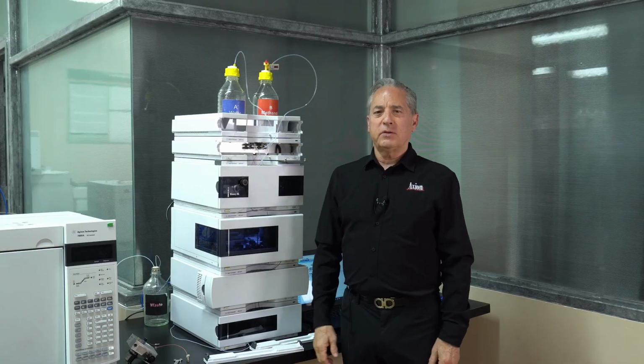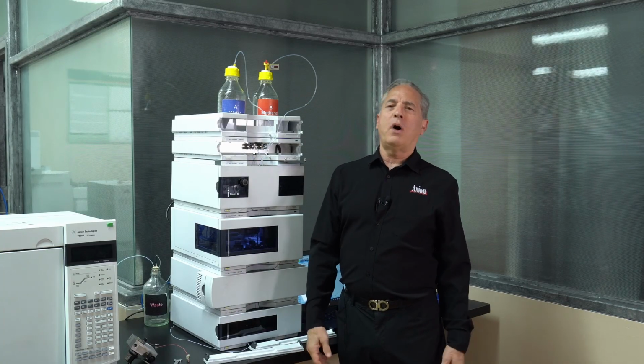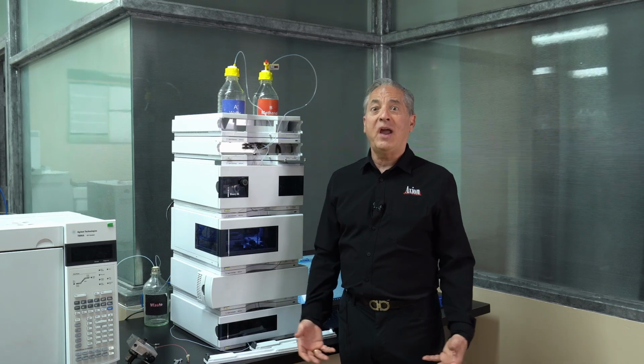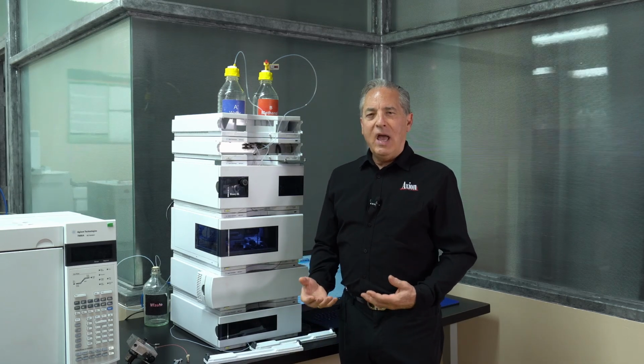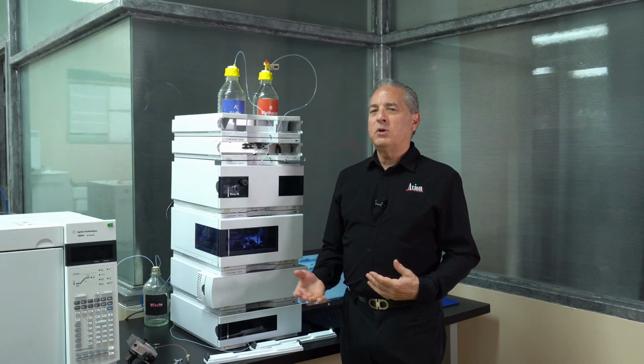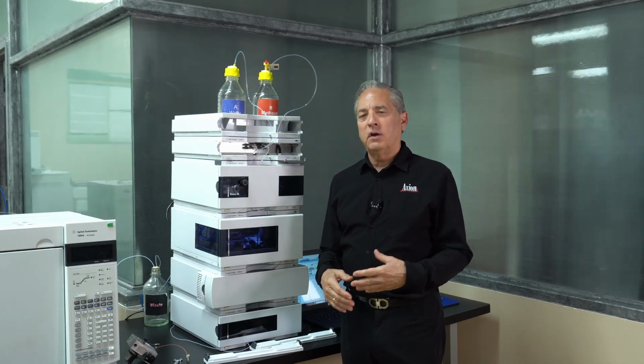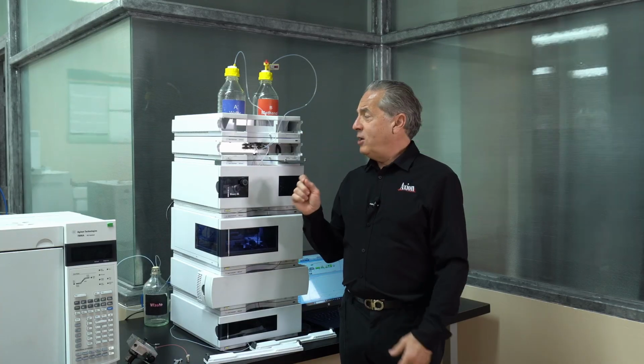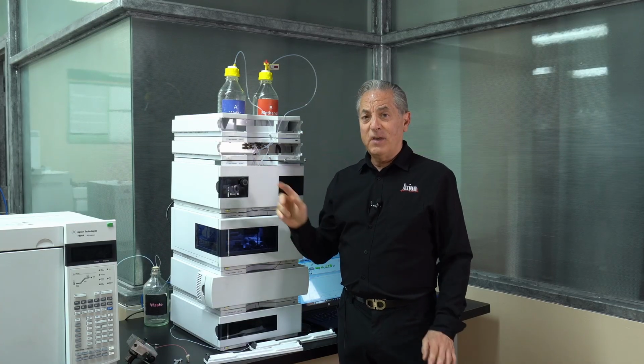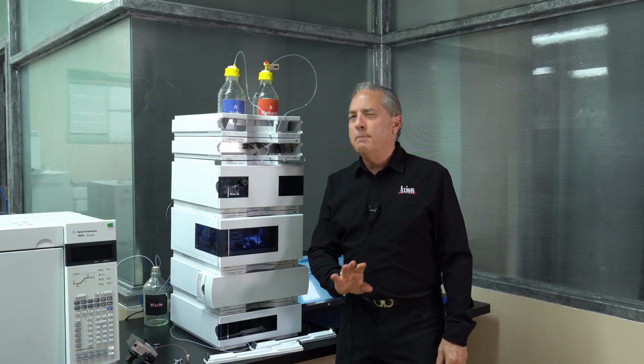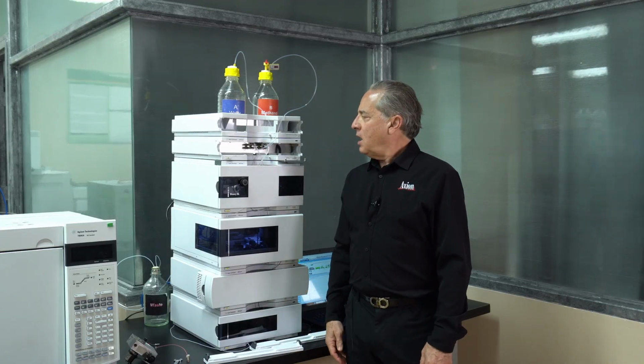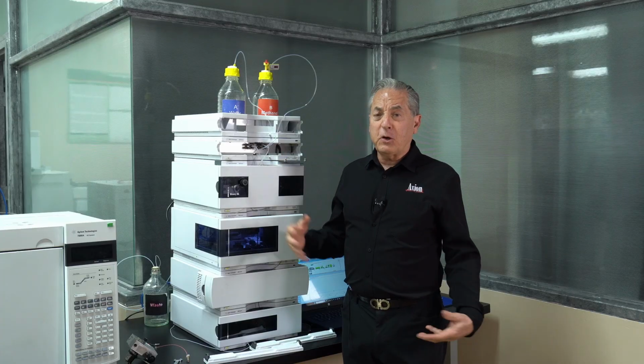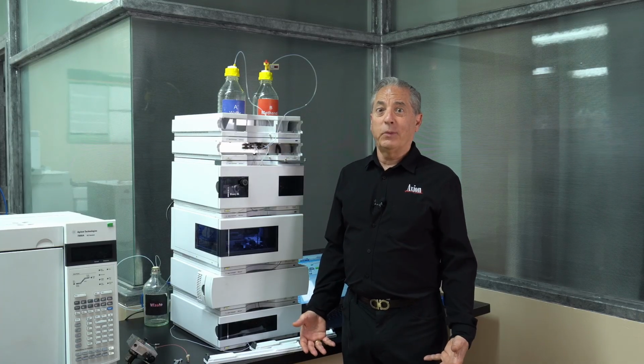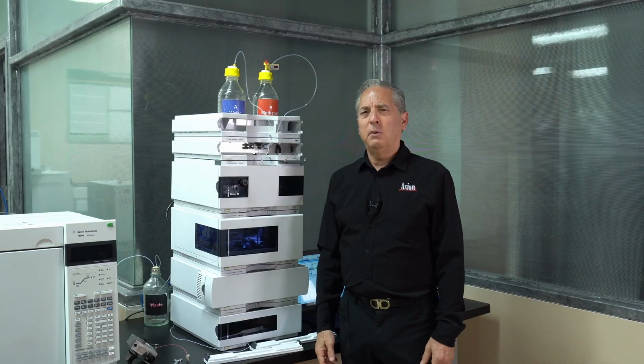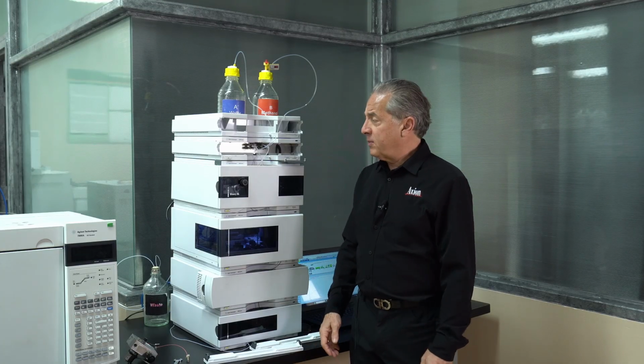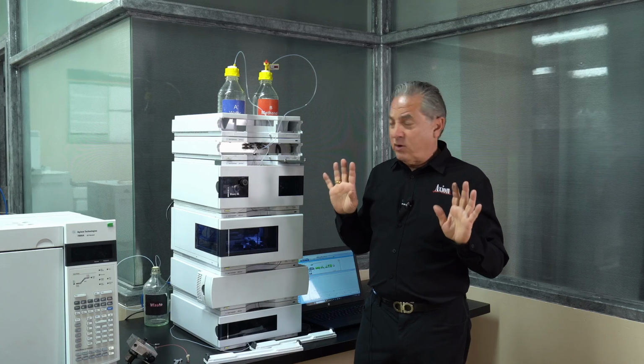If you leave A for aqueous, whether it's phosphate buffer, or acetate buffer, or pure water, or water plus acid, it doesn't matter. Water is water, aqueous is aqueous. It will keep it in solution. The only times you have problems is when you have a buffer followed by a strong solvent, or vice versa, a strong solvent followed by a buffer, and you get immediate precipitation inside the degasser. So that's the major thing that I see go wrong with degassers. Over time, when they get really old, eventually the vacuum pump could go bad. It's pretty clear when that happens. It'll give you the error, but it's not going to happen in the first 10 years of your instrument. So the degasser, not a whole lot of maintenance if you treat it properly.